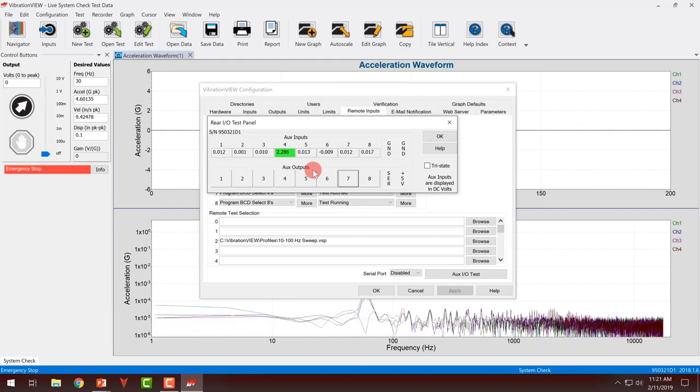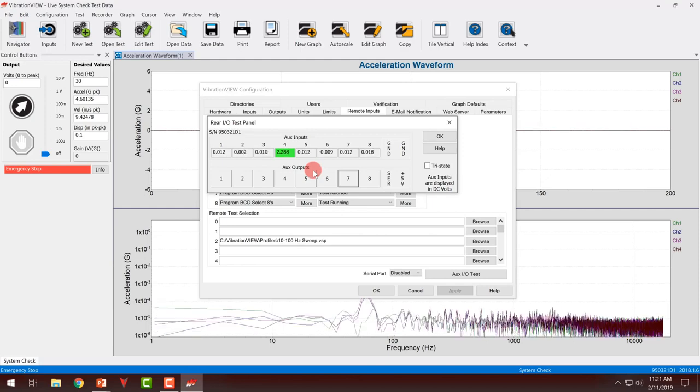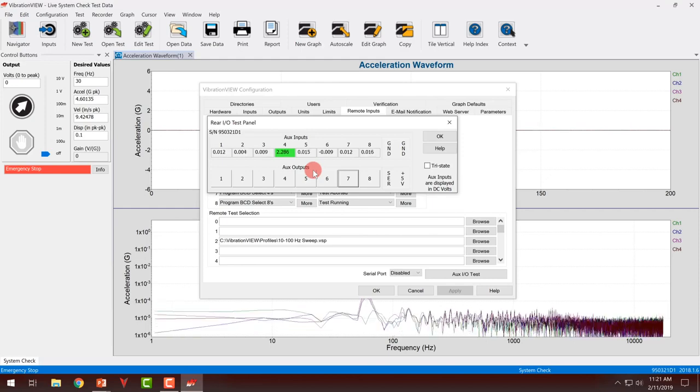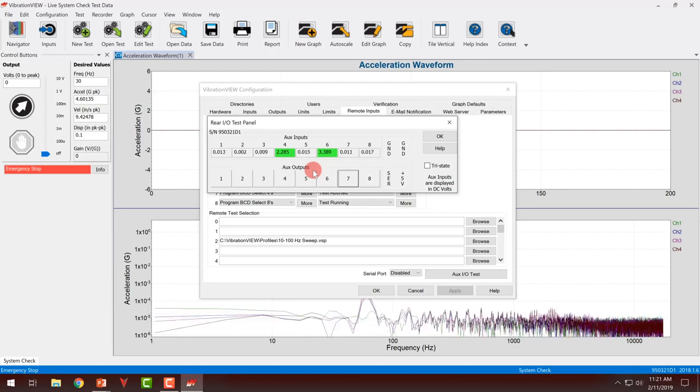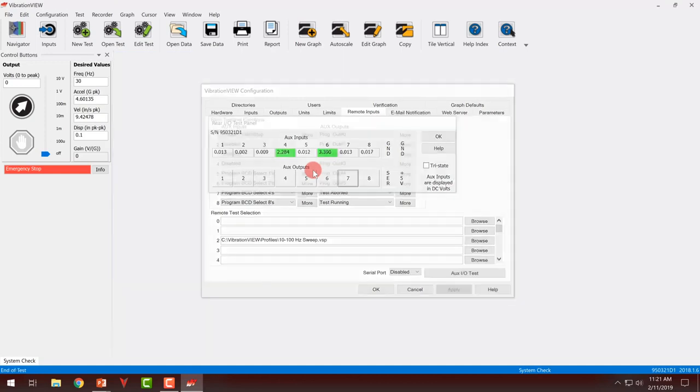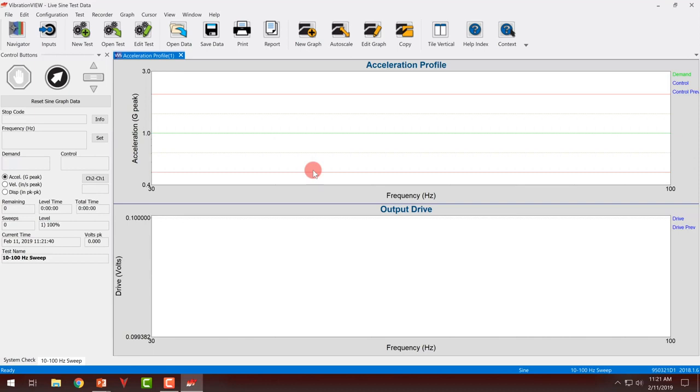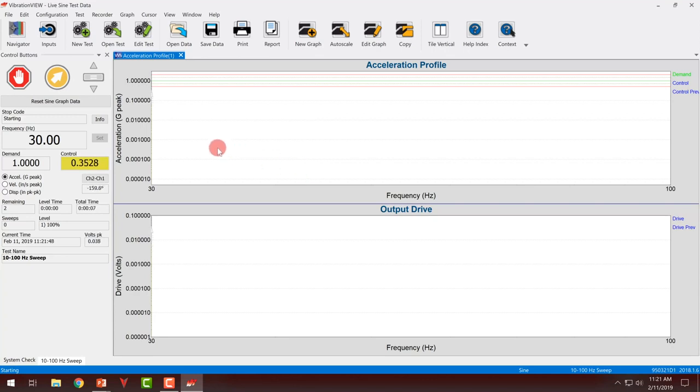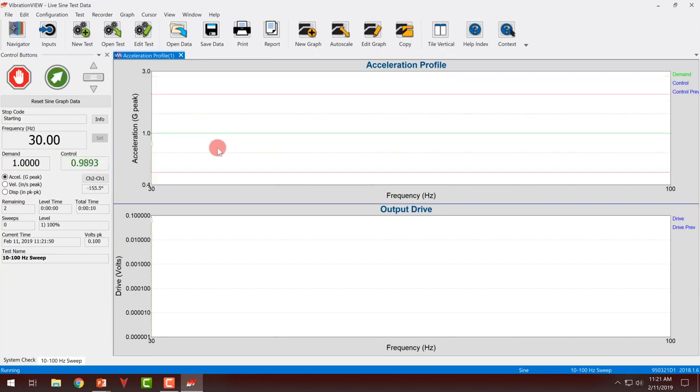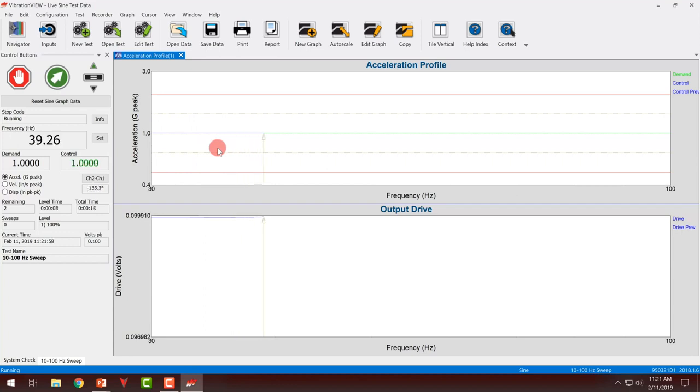I can go back to zero. If I wanted to run this test, if I go to two and then hold my program start, you can see that my test is selected and it comes up to level.